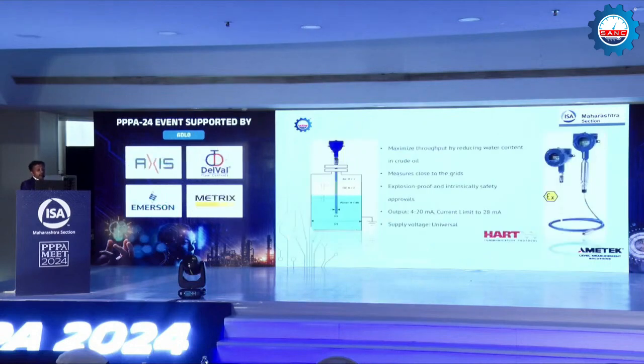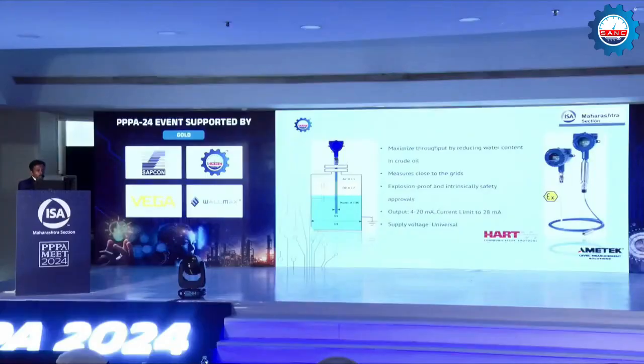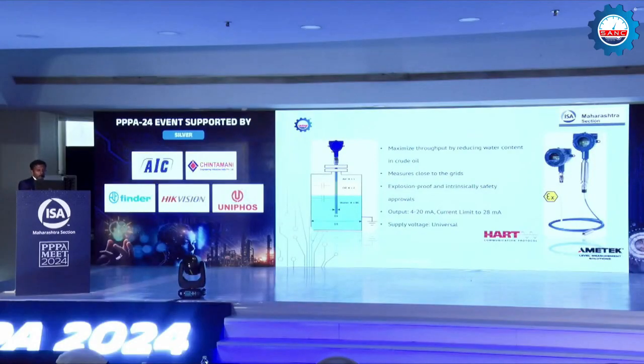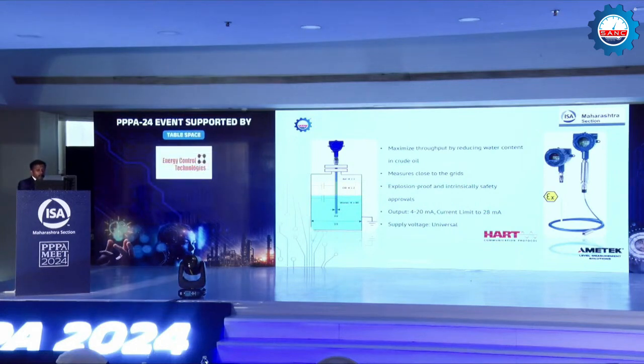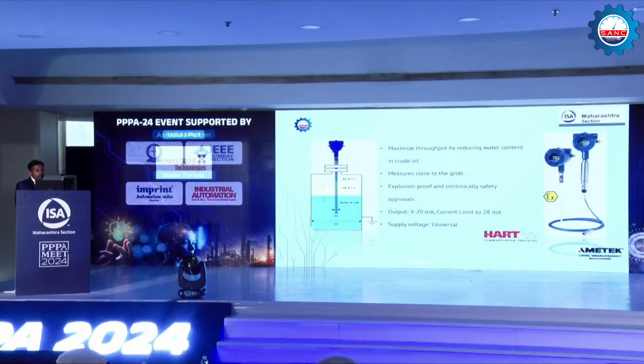If you look at this picture, the water dielectric constant is 80, and oil has 2. In the real world, we fill this tank with the actual oil up to the top level. We measure the capacitance with our transmitter, and we get some particular capacitance value. We make that the 0 level, so the complete oil becomes 0 level.